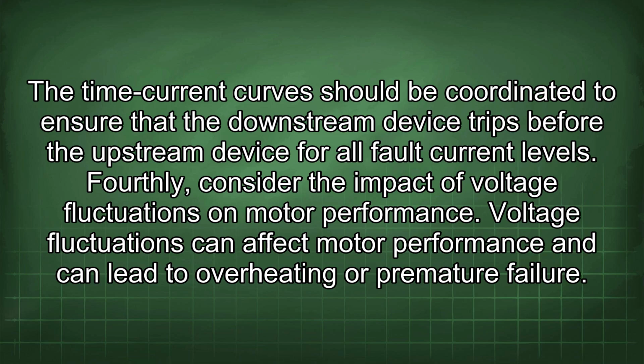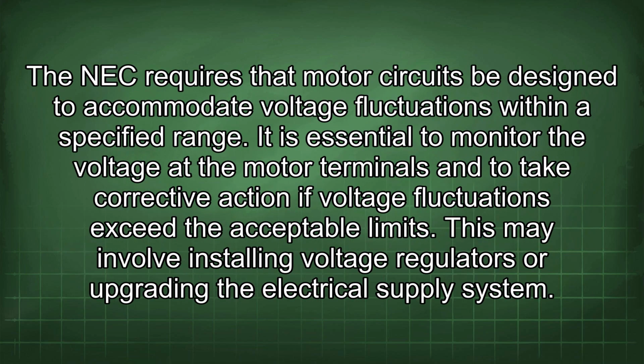Fourthly, consider the impact of voltage fluctuations on motor performance. Voltage fluctuations can affect motor performance and can lead to overheating or premature failure. The NEC requires that motor circuits be designed to accommodate voltage fluctuations within a specified range. It is essential to monitor the voltage at the motor terminals and to take corrective action if voltage fluctuations exceed the acceptable limits. This may involve installing voltage regulators or upgrading the electrical supply system.